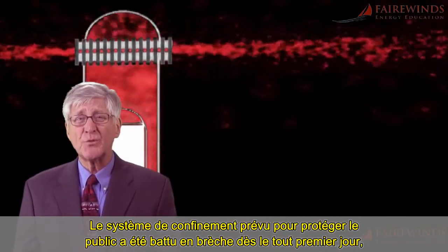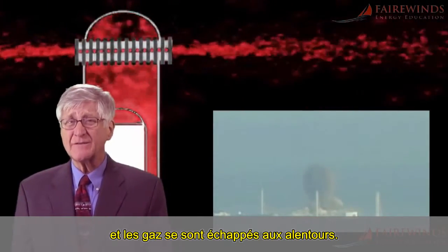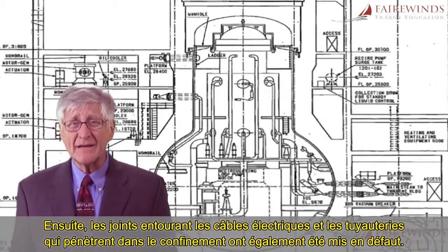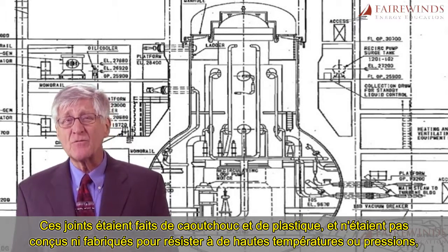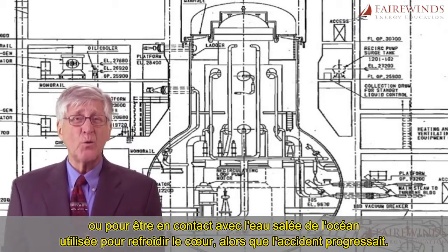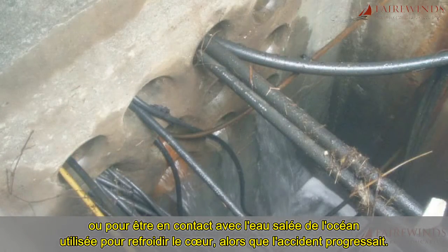The containment system meant to protect the public was breached on the very first day, and gases leaked out into the surrounding environment. Within three days of the Fukushima catastrophe, Unit 3 blew up. Next, the seals around the electrical wires in the pipes that enter the containment also failed.